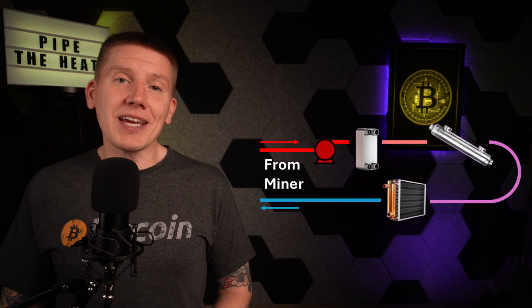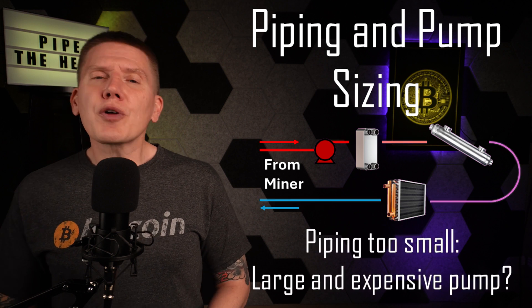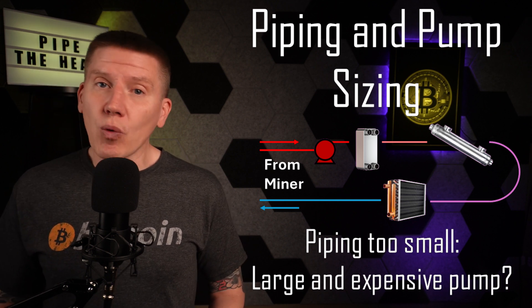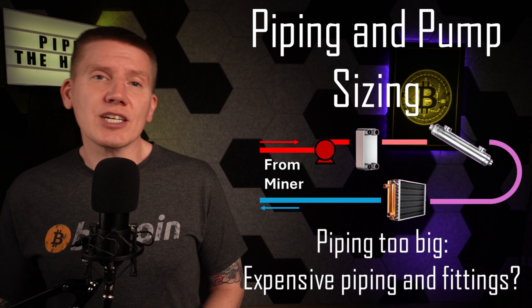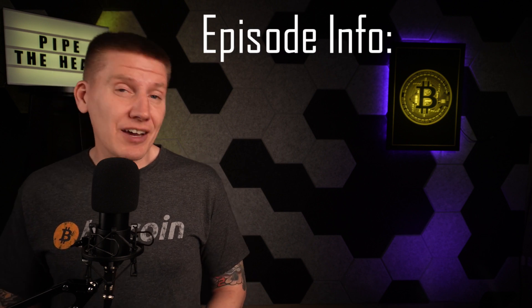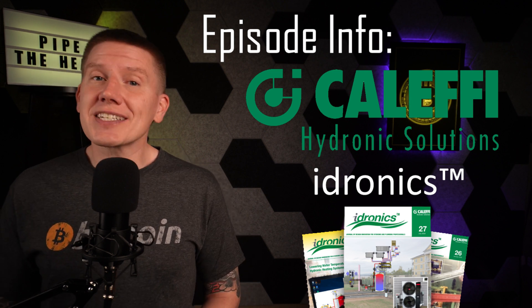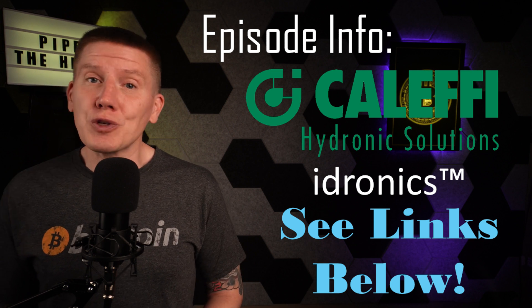In building a home heating system and routing hot fluid around a house, it's really important to get the piping and pump sizes correct. If piping is made too narrow, the pressure required to move fluid around the circuit might be so high that a really big and expensive pump is required. On the other hand, if the piping is made too large, you can spend a lot of money on oversized equipment, and it might be really hard to work out air pockets and bubbles out of the system. Just like in past episodes, I'll be pulling my information heavily from the Caleffi Hydronics articles. I really can't recommend these enough — they are a fantastic resource for designing and building a home Bitcoin heating system. I've got links below that will take you to the exact articles used for this episode.